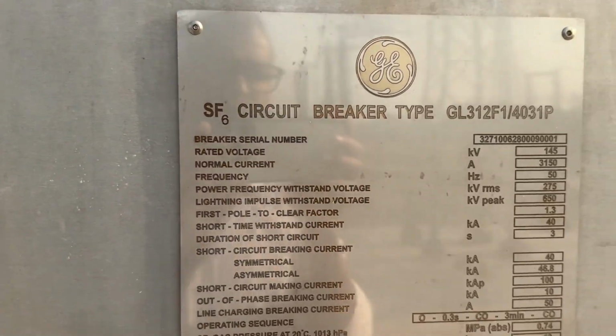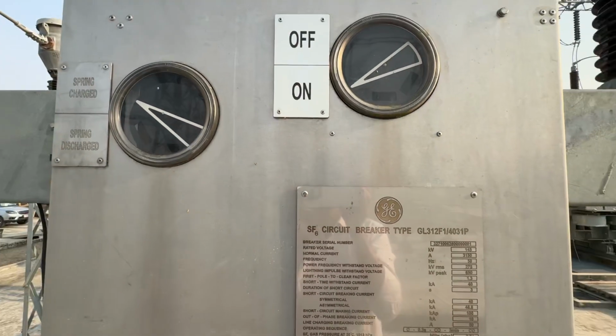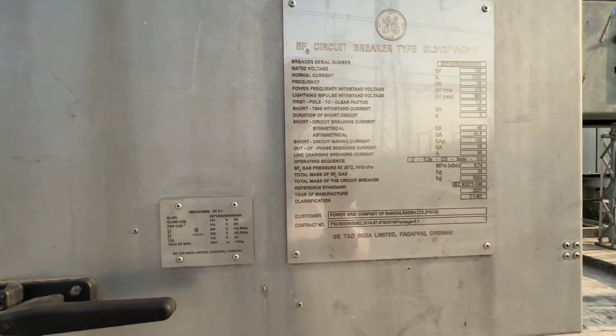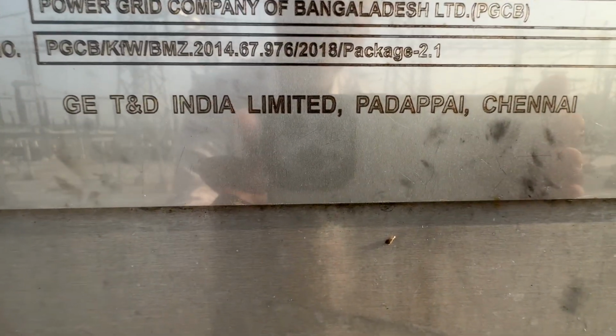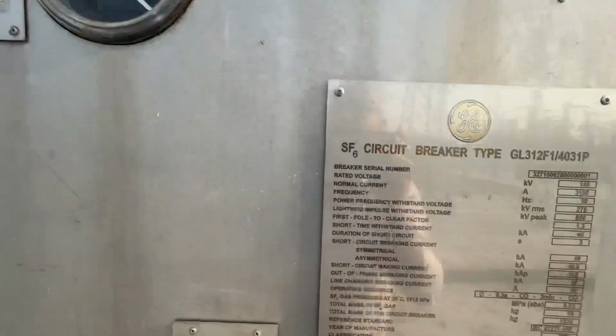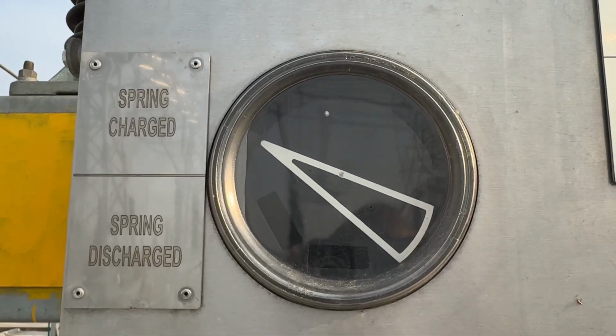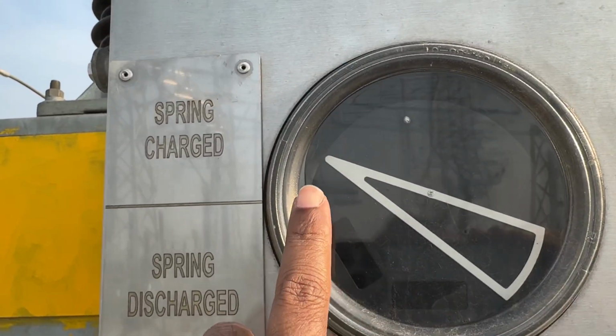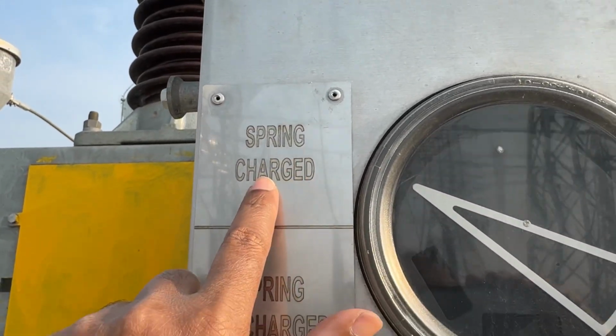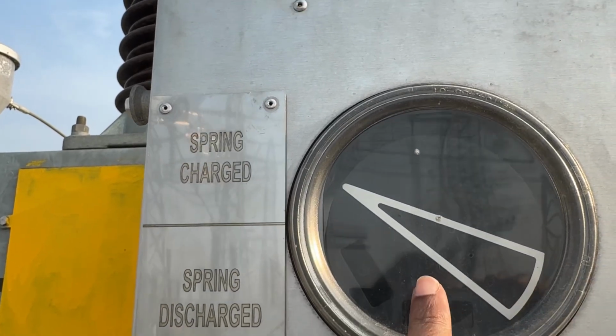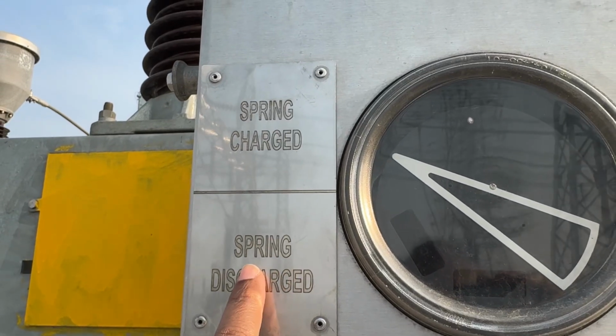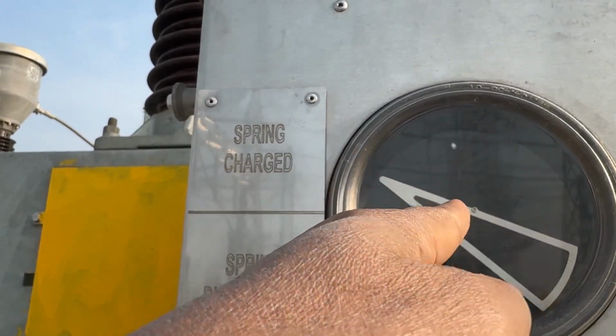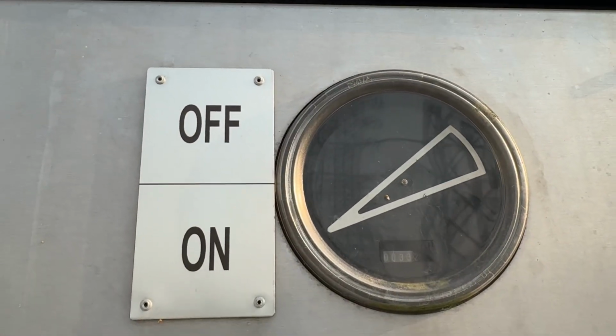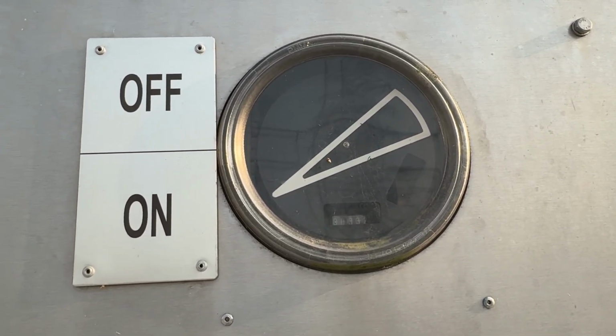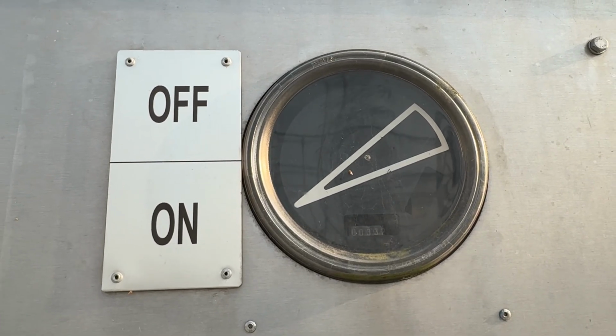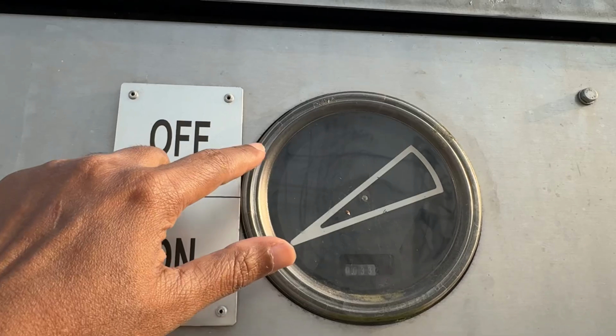Okay, let's see the circuit breaker. This circuit breaker mechanism is made by GE T&D India Limited. Okay, this is the spring charge indication. When the spring is charged, the indicator is shown here, in this direction. If the spring discharges, the indication will come to here. It will rotate this way. And this is the indication of on/off. The circuit breaker is now closed, so it is showing on. When the circuit breaker opens, the indicator will rotate to this direction.